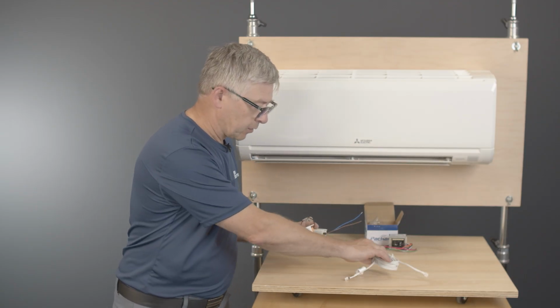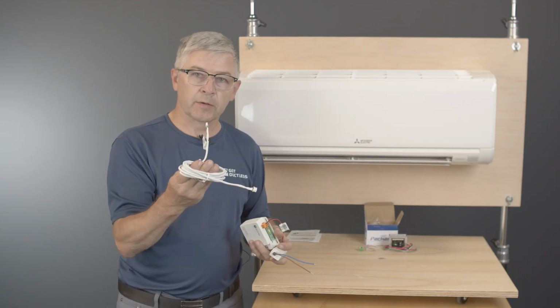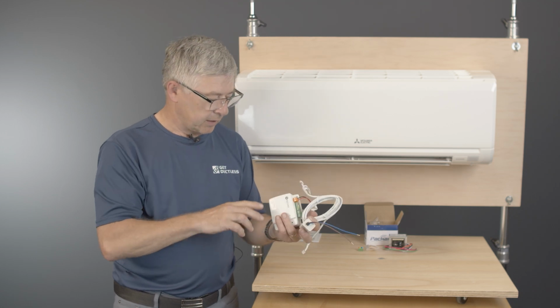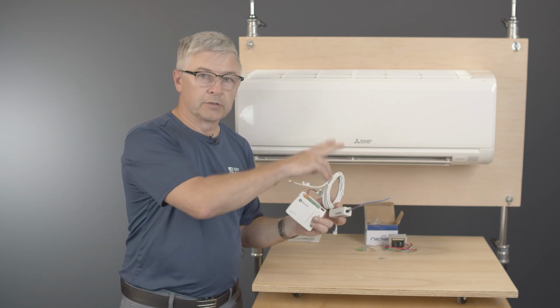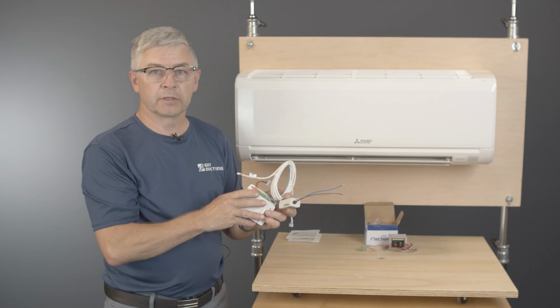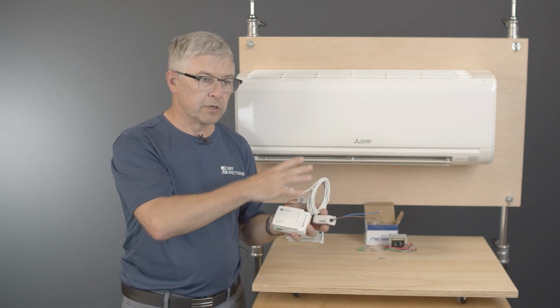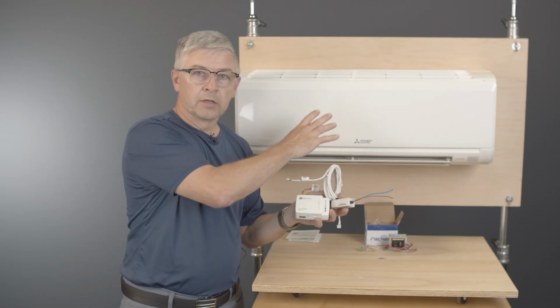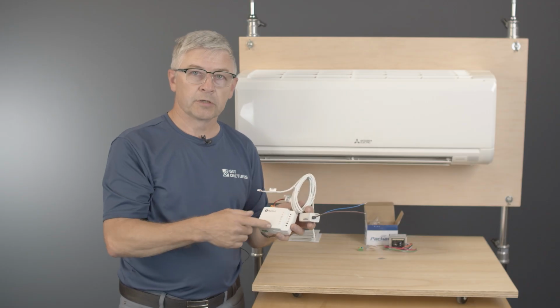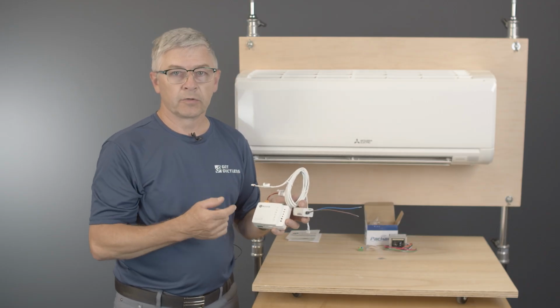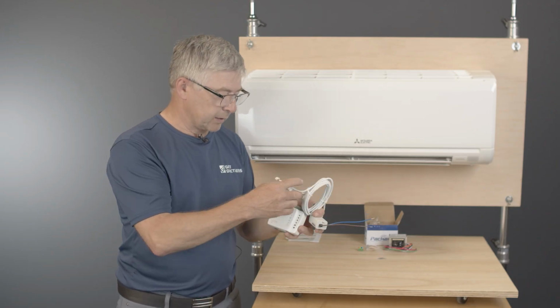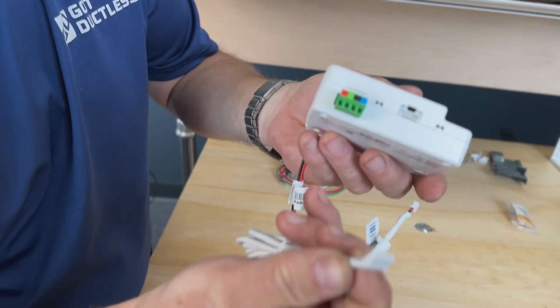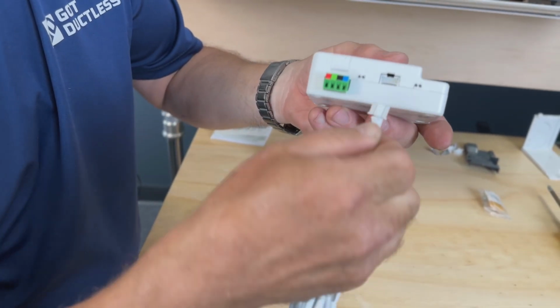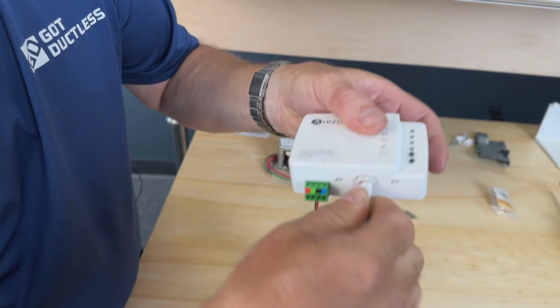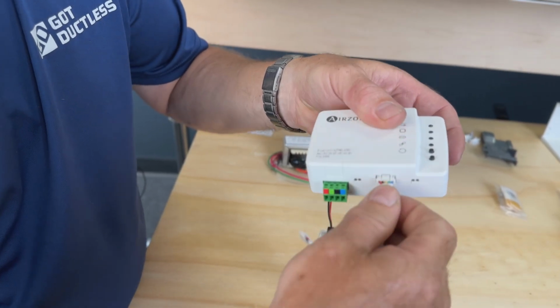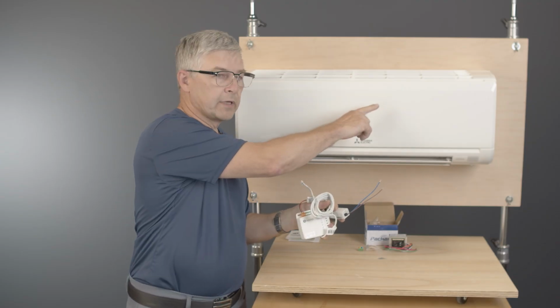Now the next cable is a communication cable, and it allows the adapter to talk to the indoor unit. This adapter converts the Mitsubishi signal to the non-Mitsubishi language 24-volt controls. We connect this cable to the small hidden port on the bottom of the adapter, and the other end connects to the control board on the air handler.